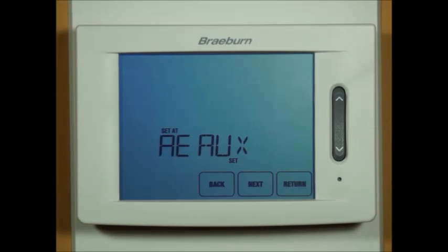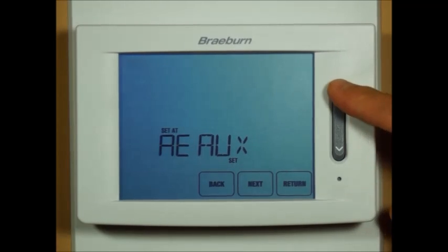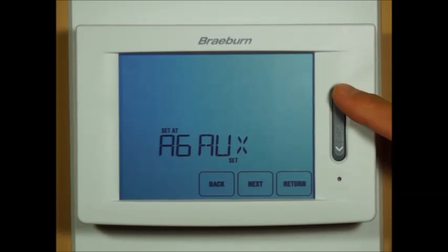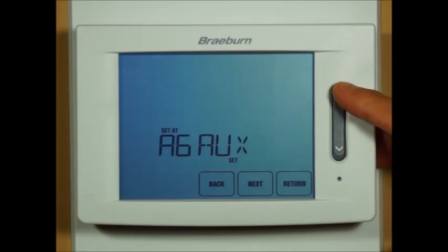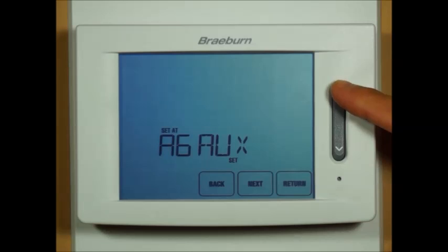Auxiliary heat electric or auxiliary heat gas — this is basically for your fossil fuel control. If you select gas, then on a call for auxiliary heat your compressors will turn off after 60 seconds.